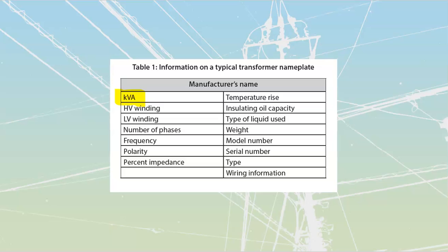You could be passing through relatively few watts and loads of VARs, but you'd have X amount of kVA, or you could be passing through a large amount of watts and a low amount of VARs and get the same kVA. It just makes it easier for them to write this without having to add in angle thetas, etc. It refers to the total kVA that the whole transformer can pass through.